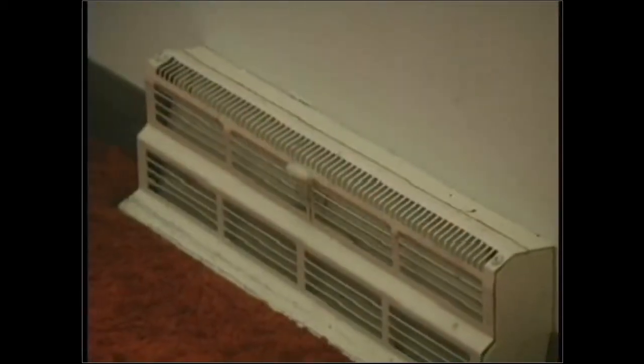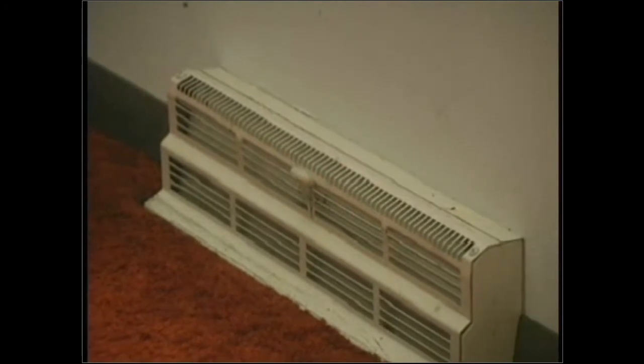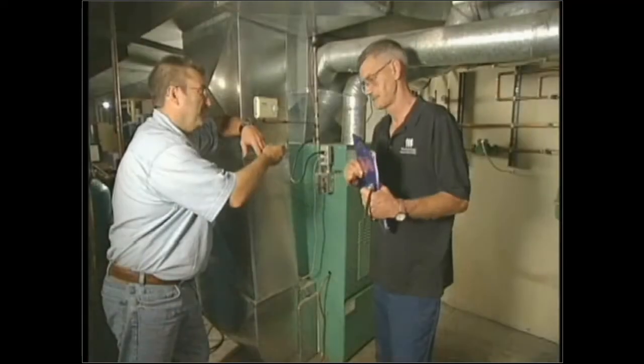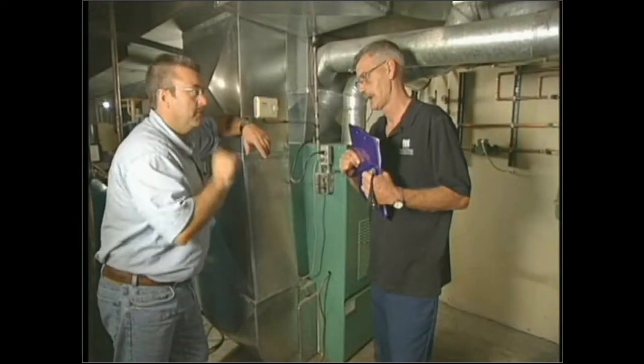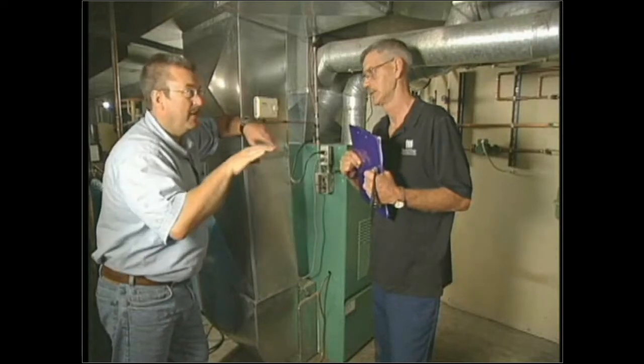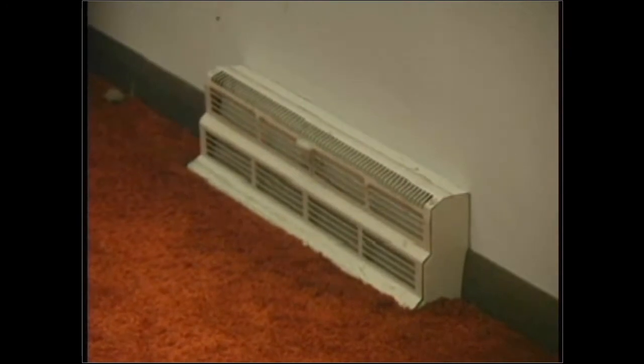Okay, so that sounds like a pretty important differential between inspecting a gas-fired unit and an oil burner. Make sure you pay close attention to those supply registers. And you said right across the top, rub your finger. It's going to smear if it's oil. That way you're not smearing it across the wall.